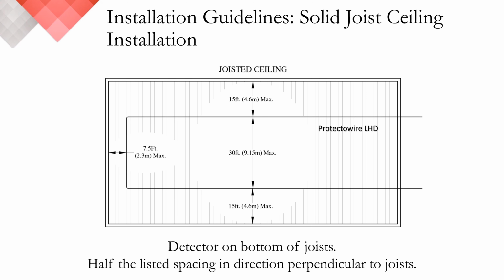With solid open joists, greater than 4 inches from the ceiling and less than 3-foot spacing, or other similar structures, heat travels freely down the joist channels. However, heat has trouble spreading across the joists, so the distance in this direction must be reduced. The Protectowire shall be mounted on the bottom of the joist, and the spacing of the detectors on all runs perpendicular to the joist shall not exceed 50% of the smooth ceiling spacing.